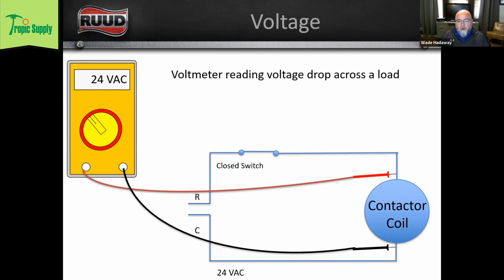So we've got 24 volts going through this contactor coil. And when we put our meter on either side of the coil, we can see that our voltage drop across that coil is 24 volts.